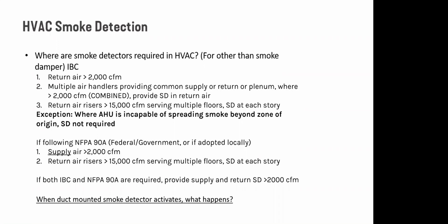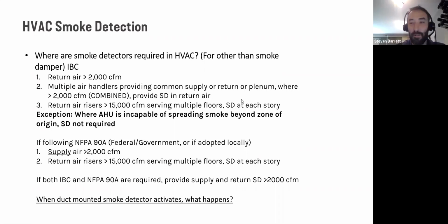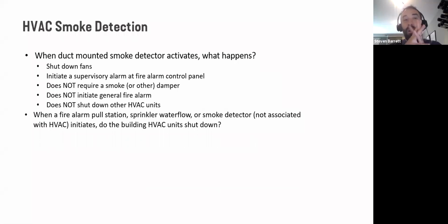So, all right, that looks like most everybody. Okay, well, you guys fell for the trap. All of the above is not the correct answer. The correct answer is to shut down the fans. The giveaway could have been the close all fire and smoke dampers with the AHU. So when the duct-mounted smoke detector inside the unit activates, shut down the fans. It initiates a supervisory, not an alarm. So supervisory means that the fire alarm control panels know something's going on. They make a really loud buzz at the panel itself. You're probably going to get an alarm on your BAS. It's going to notify the fire department, but it's not going to initiate a general building evacuation.